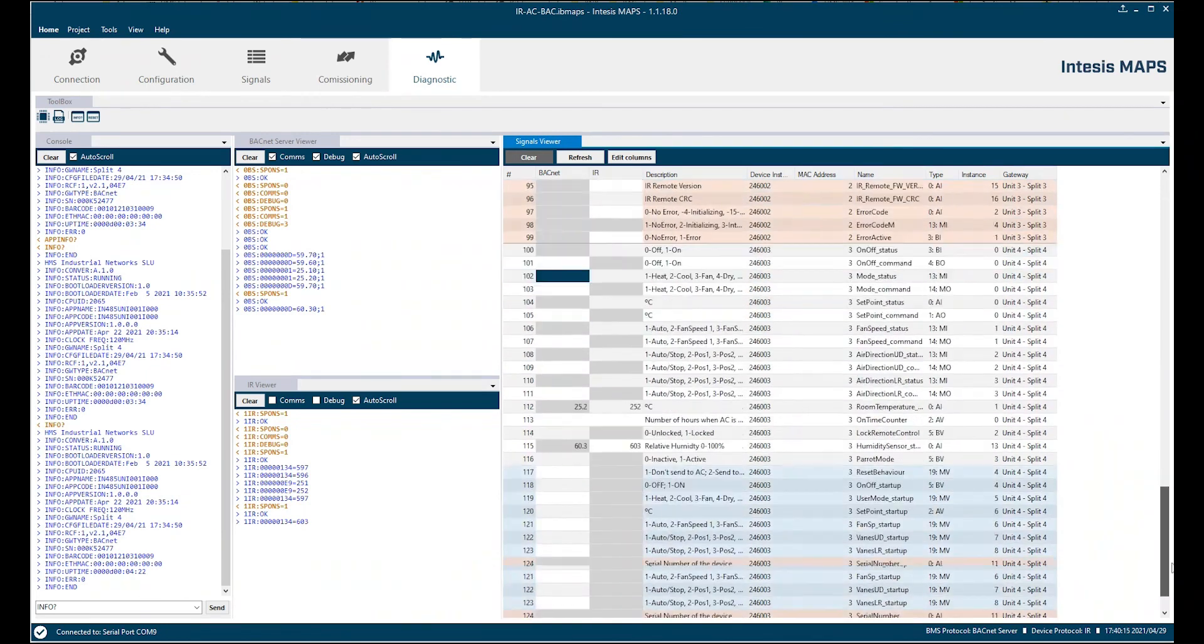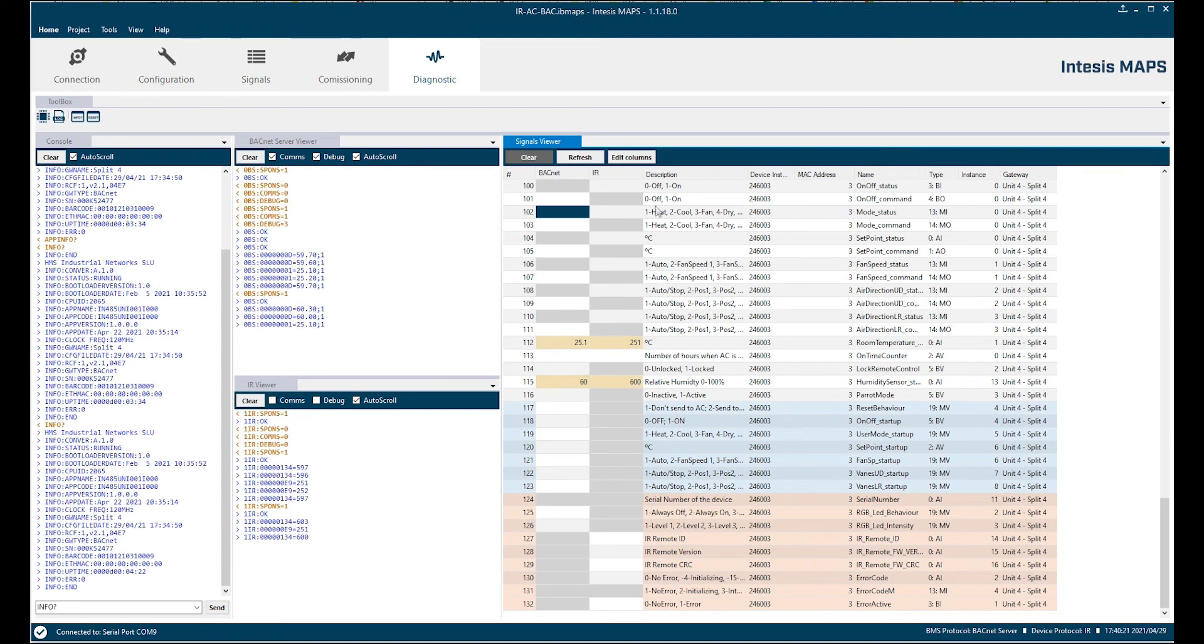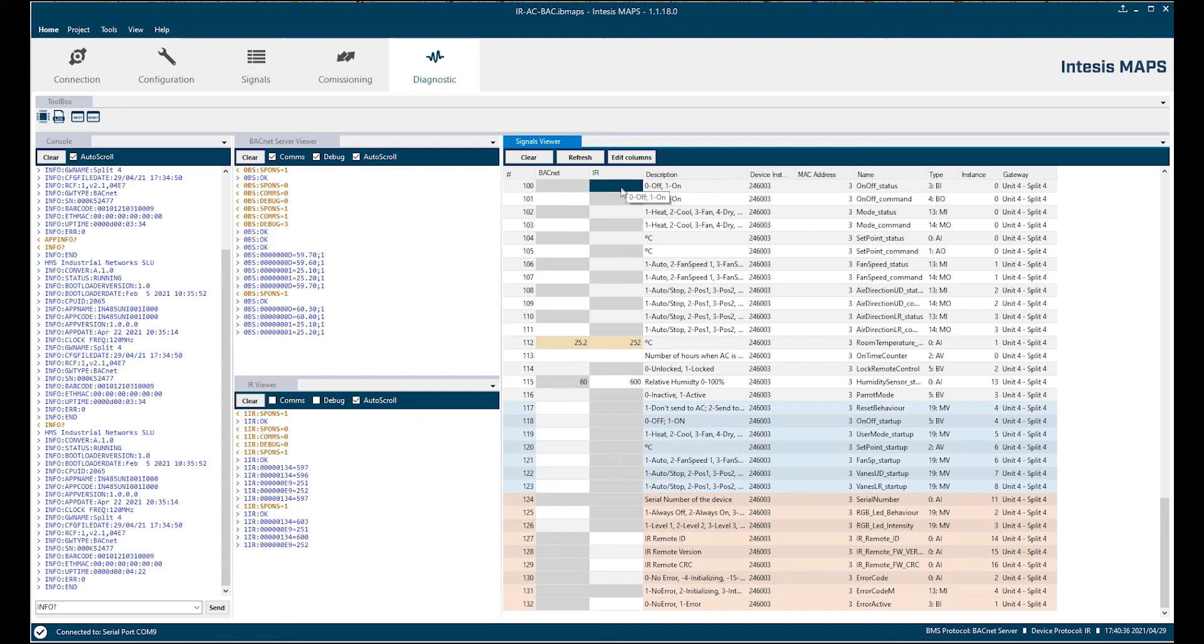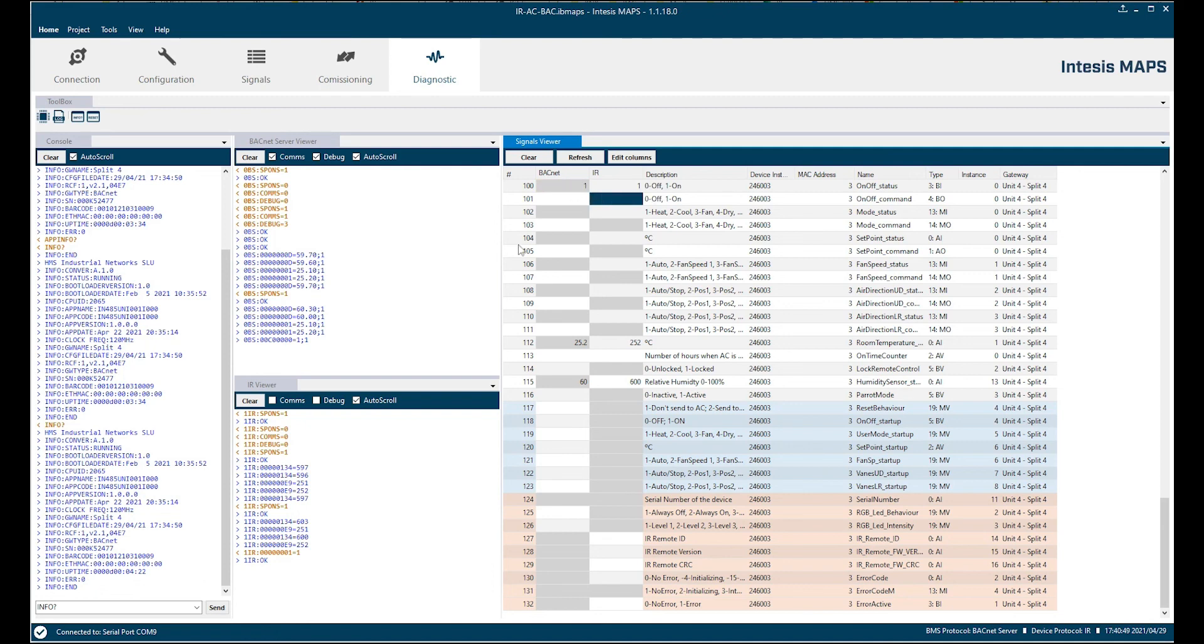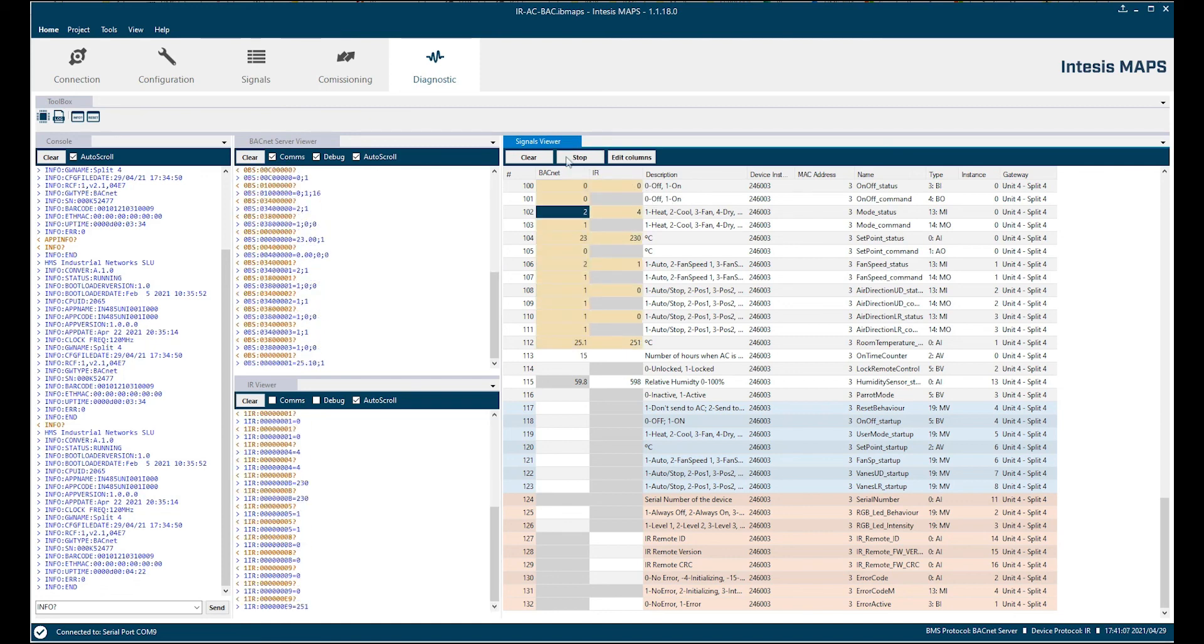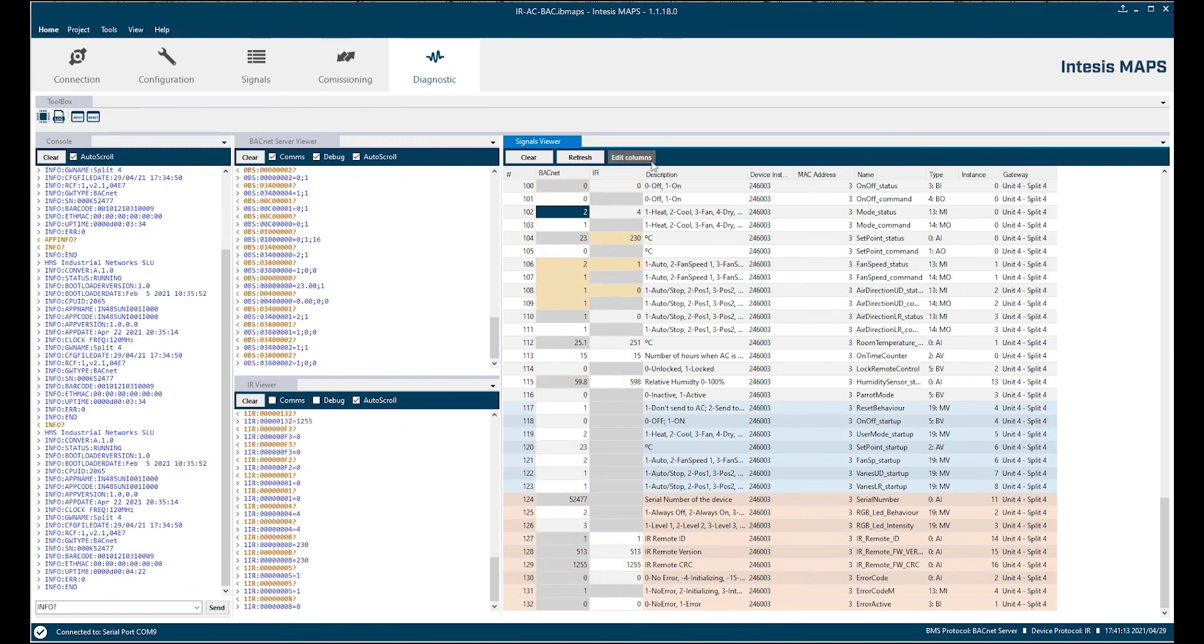I go down here in the signal viewer. Here we have all signals we have in our project. All objects. And for example I have here a BACnet side and I have again the infrared side. And if I want to change something on one side, let's say I change on the infrared side 1. This is a simulation. Then clicking enter it appears also on the BACnet side. So this communication works. Same in the other direction. If I send for example from the BACnet side a zero on the on off command object, it will be received on the infrared side. We have here also the refresh button to refresh all values of all our objects. We have here also the possibility to edit the columns, make them visible or invisible.